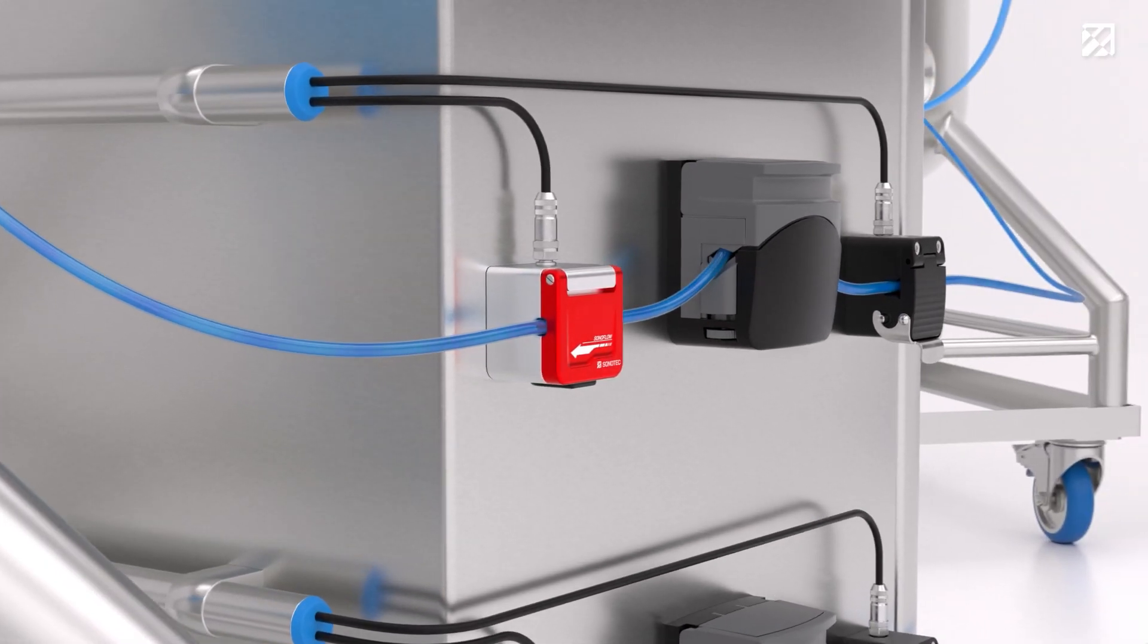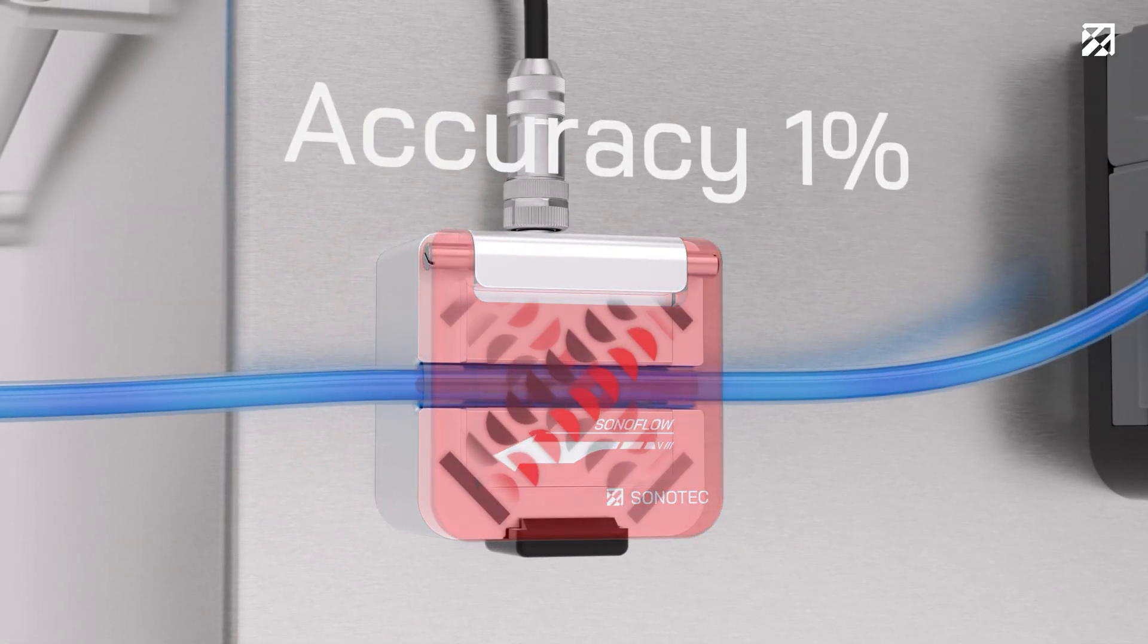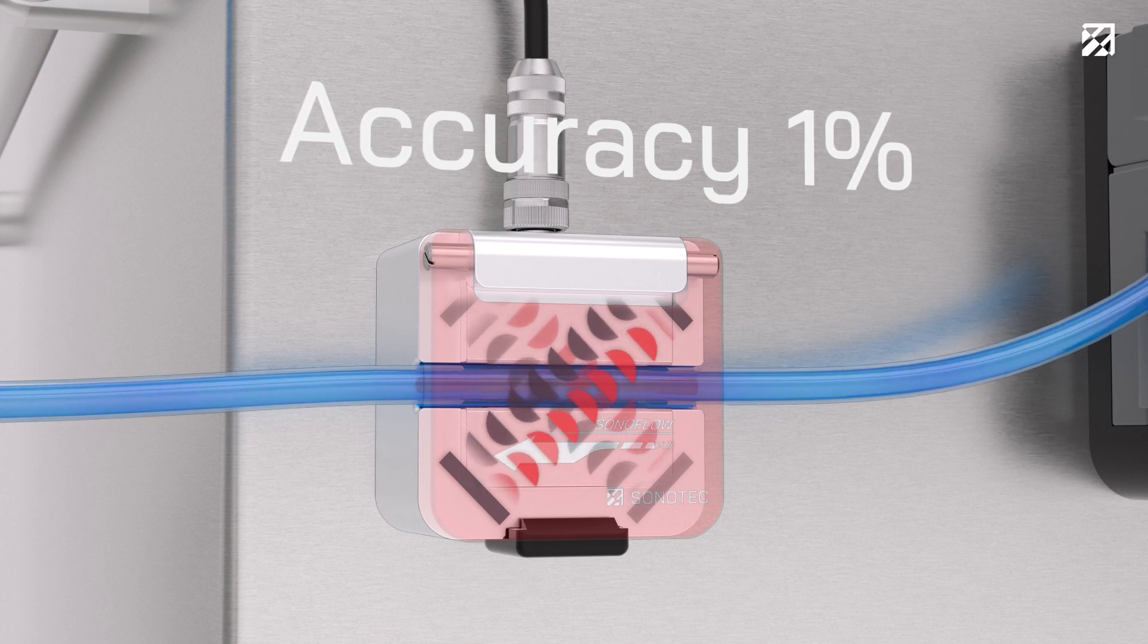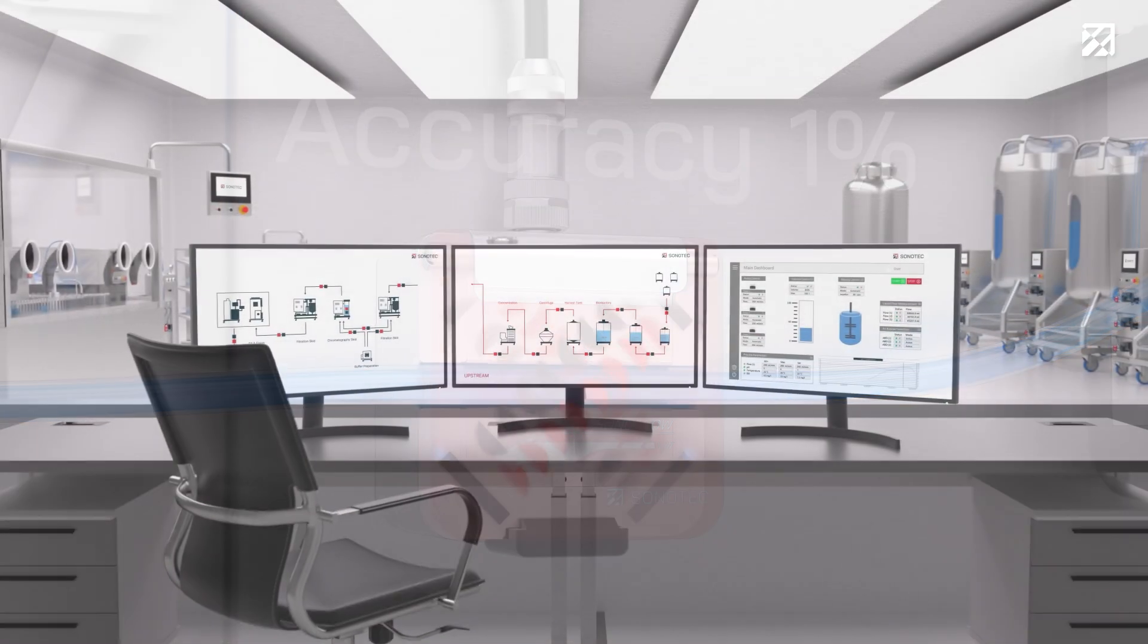We measure the flow through the flexible tubing via the ultrasonic transit time method. This way, we combine highest accuracy, reliability, safety, and usability.